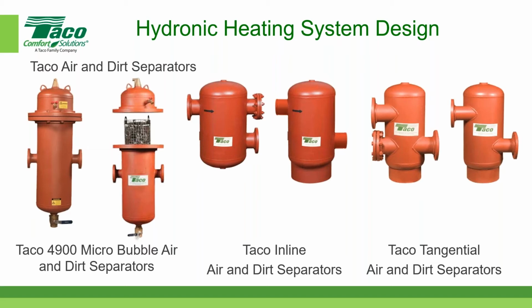As far as getting rid of air, air is the enemy. When you fill a piping system, even if you fill it to the very, very top, and there doesn't seem to be any room, there is air in solution. So the water or the water glycol actually has air trapped in solution. And over time, that air will come out of solution. So you want to remove it from the system. And that's the main purpose of an air separator. So hopefully I've covered the majority of the operations.